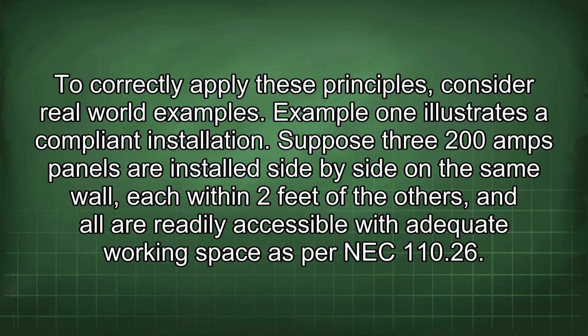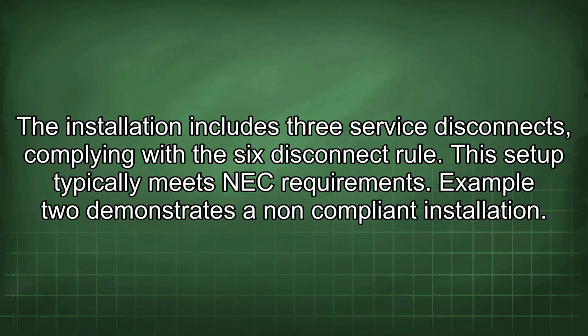Example 1 illustrates a compliant installation. Suppose 3 200 amp panels are installed side by side on the same wall, each within 2 feet of the others, and all are readily accessible with adequate working space as per NEC 110.26. The installation includes 3 service disconnects complying with the 6 disconnect rule. This setup typically meets NEC requirements.